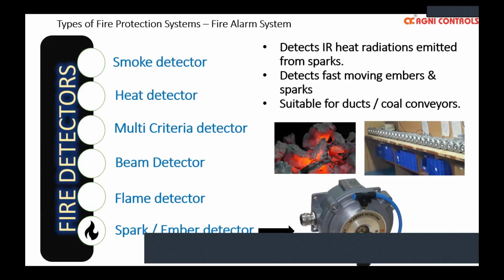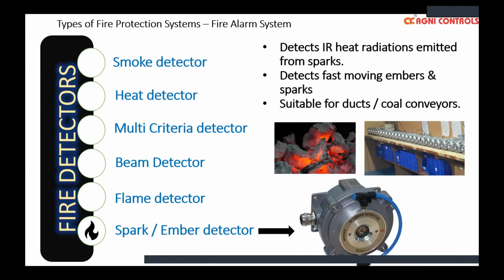So these are the flame detectors. Now coming to the final type of detector which is available, the spark or ember detectors. Here I have an image of an ember. This is not an actual flame. This is a smoldering fire. The best example of a smoldering fire is the tip of an agarbatti. That is not an actual flame, but these detectors are designed to detect moving smoldering fires on a conveyor, especially on coal conveyors.